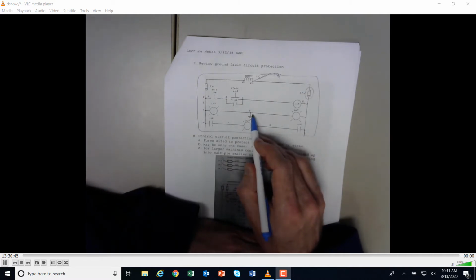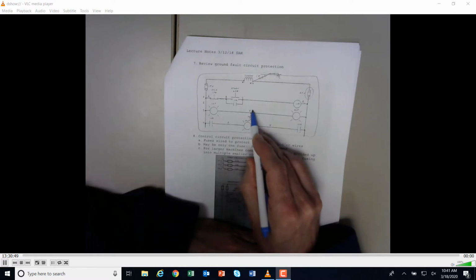But we don't have that, so we have an ungrounded secondary, so we need two fuses, and we need a way to monitor if there is a ground fault. Because this system right here is not being brought down to the earth in the same way as if it were grounded here on the secondary. So we would have a ground point here. This point here would be connected to our system or our panel, and it's going to have a load on either side. So if we get any kind of a short or a ground fault, it is going to be affected by this point.